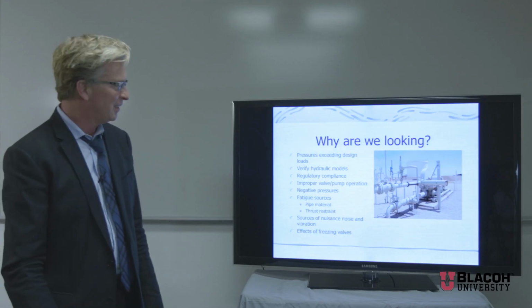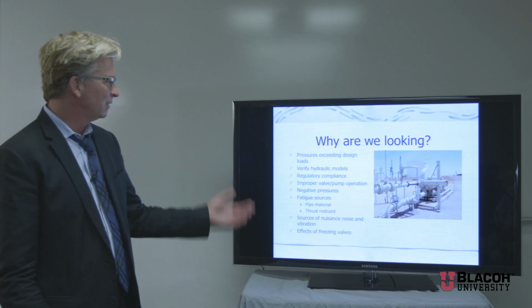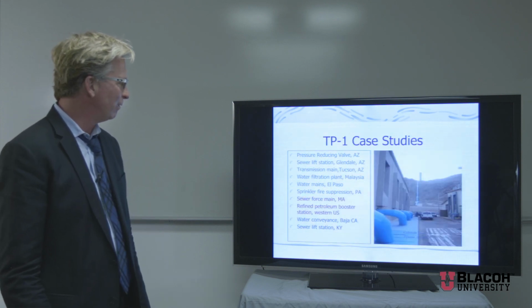This is why, for everything about the surge analysis in the model, we have to have all the components, all the pumps. So many times I've gone into a pump station and they've got 3 pumps and then a fire pump that's tied into the system. And I'm like, I need those 3 pumps and that fire pump curve because that's the worst case scenario. Because we'll go back after the fact. It's like, oh, well, they only had a problem once a month, and it was once a month that they tested that fire pump. So again, your input data is critical to the model, and again, use transient monitoring equipment to verify it in the field.